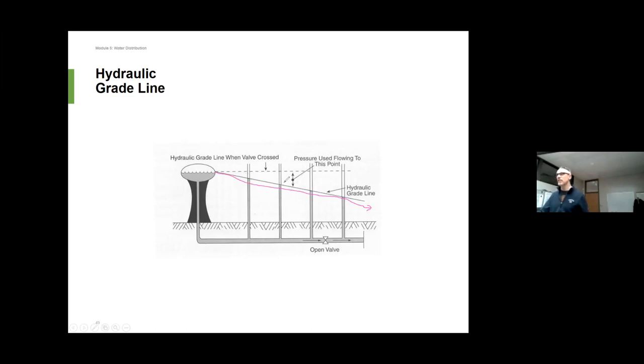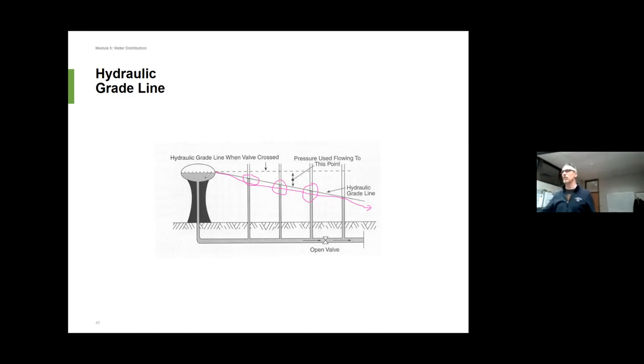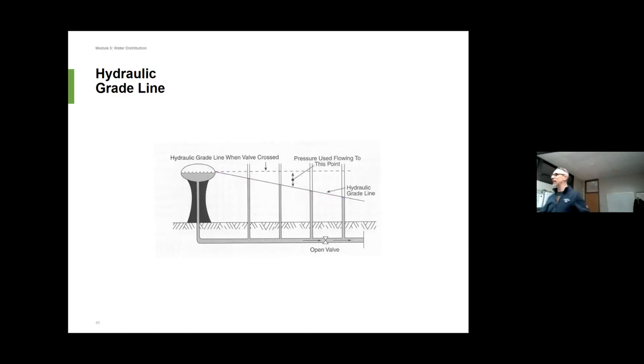One of the biggest things I see is people design systems or size pumps without accounting for losses, and then it doesn't work. They'll build a house and put a washer on the top floor based on static pressure, but as the reservoir level starts to go down, so does the hydraulic grade line. Over time you could actually lose water service to the upper parts of some buildings — that's because the hydraulic grade line lowers as the water level drops.